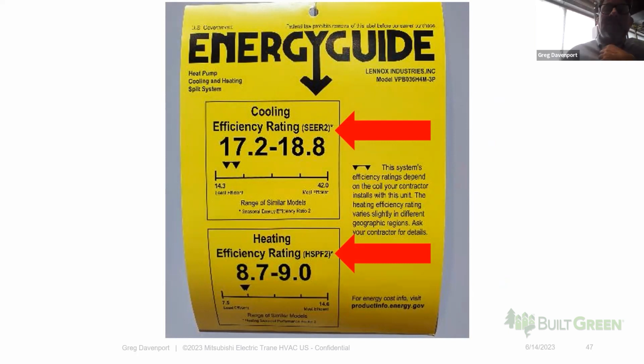You can see on this yellow sticker here that a lot of people are familiar with - the only way to tell that you've moved from the old HSPF rating system to the new HSPF 2 rating system is right down here, and it's kind of in small print. I will tell you the new HSPF 2 testing protocol is more realistic and it's better. The way they did it before was kind of not a real world static pressure for all the ducted systems. This is a much more realistic energy efficiency measure, so in the long run, I think we're all going to be better off with it. In the short run, it's going to be more growing pains as we make adjustments with our new code and with HSPF 2.